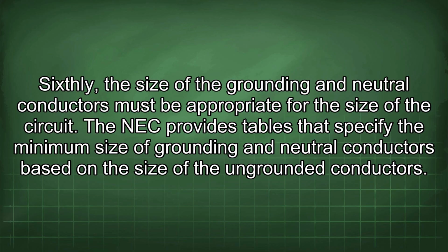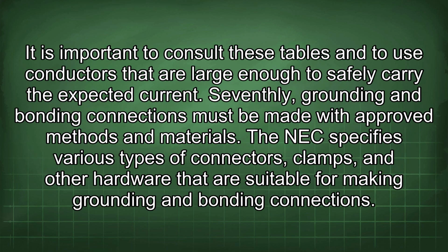Sixthly, the size of the grounding and neutral conductors must be appropriate for the size of the circuit. The NEC provides tables that specify the minimum size of grounding and neutral conductors based on the size of the ungrounded conductors. It is important to consult these tables and to use conductors that are large enough to safely carry the expected current. Seventhly, grounding and bonding connections must be made with approved methods and materials.